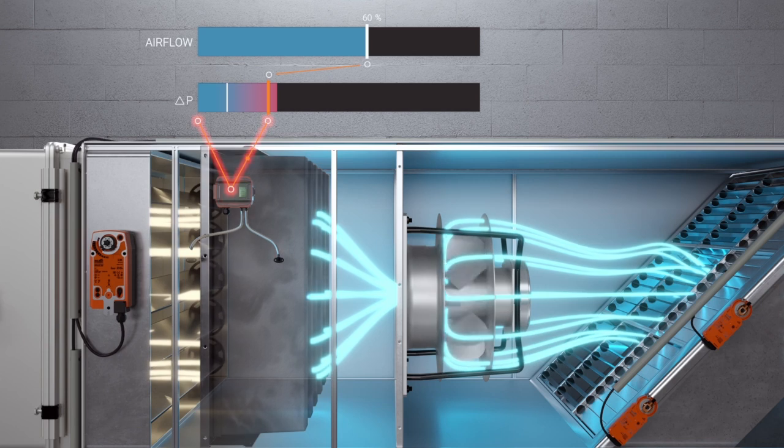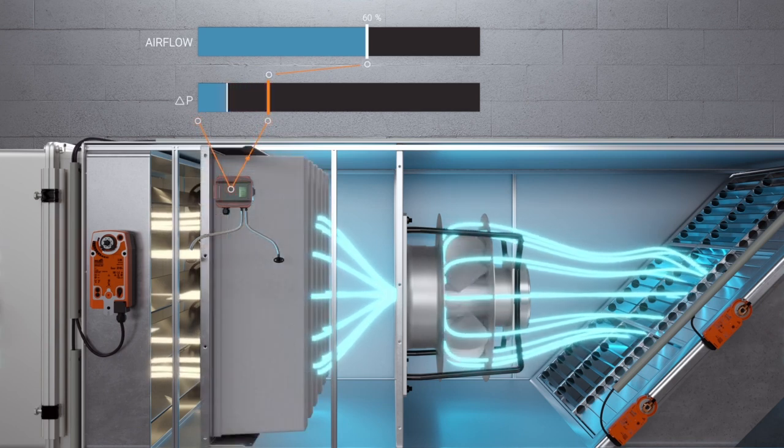To decide whether a switch or a sensor should be used, the intended operating mode of the air handling unit must be taken into account. In summary, the following three points are decisive: Differential pressure switches are suitable for filter monitoring in air handling units with constant volumetric flow. Differential pressure sensors always show the current differential pressure in any operating situation. And if the differential pressure and the air flow volume are known, then the condition of the filter can be reliably assessed even at partial load.